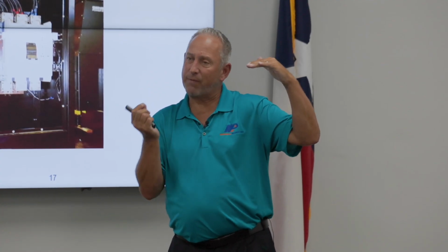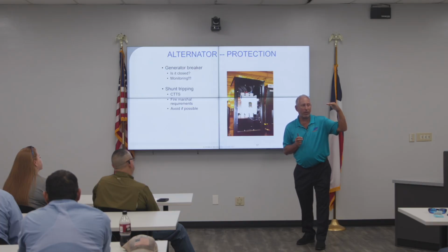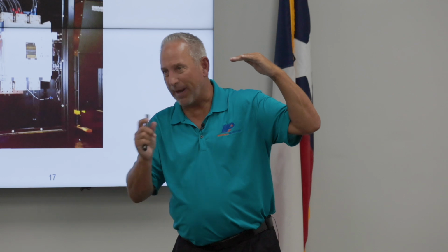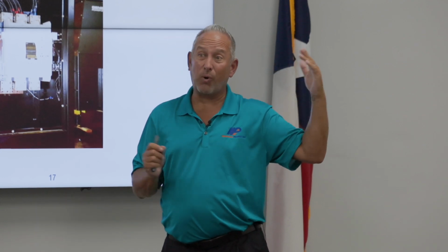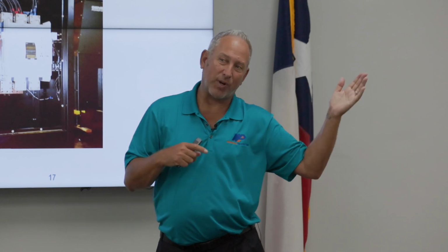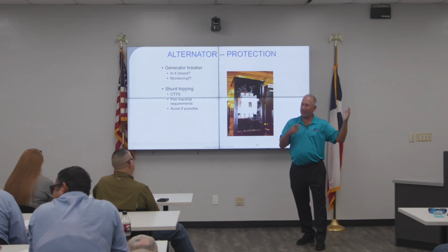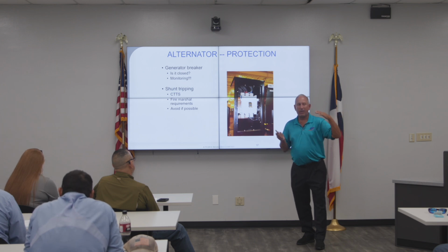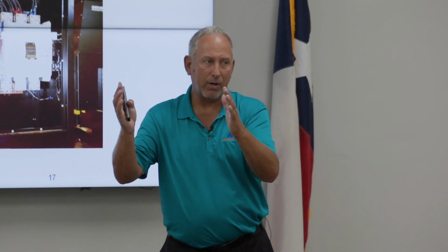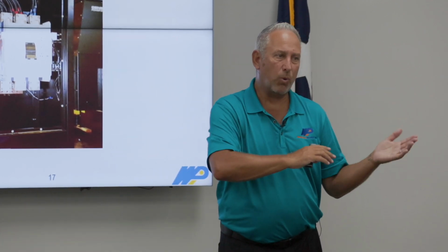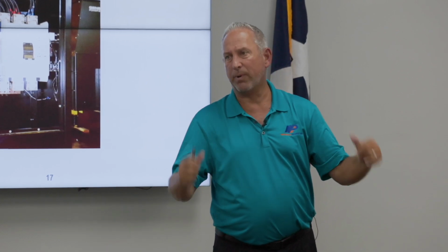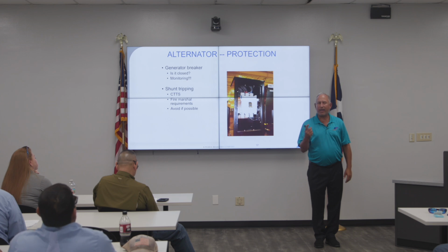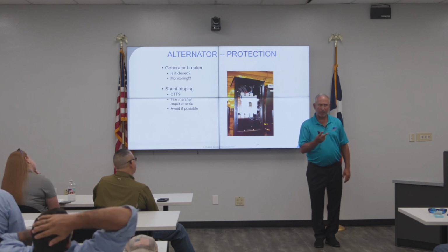So let's say you have your timer set for 15 minutes. 14 minutes and 33 seconds into it, it goes out of spec. It goes back to 15 again. So a lot of times we'll get a call going, hey, utility's been back, but the generator hasn't transferred back yet. Like, well, has it been there reliably for the amount of time? So when it transfers back, what does it do? It breaks from the generator and goes to the utility. So what that causes is another outage in your building, right? So every event, you will lose power twice. The first time, because the event happened, and the second time when you're transferring back to utility.